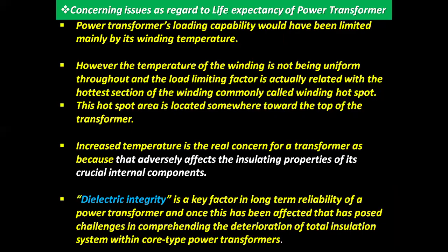Concerning issues with regard to life expectancy of a power transformer. A power transformer's loading capability would be limited mainly by its winding temperature. However, the temperature of the winding is not uniform throughout, and the load limiting factor is actually related to the hottest section of the winding, commonly called the winding hotspot. And this winding hotspot area is located somewhere toward the top of the transformer.